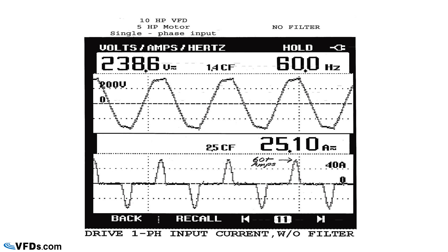Now let's look at diagram 2. This is not so clean. It can be referred to as corrupt power, dirty power, polluted power. You'll notice that we have current on the bottom and voltage on the top, and the current is created in short pulses. This is how variable frequency drives work — they gulp power in pulses, and whenever there's a pulse, it drops the voltage. You can see that the voltage is dropped every time there's a pulse, and this creates flat topping. This is some seriously polluted power.